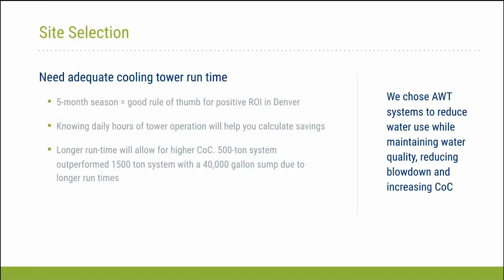So, for example, you can have a 500-ton tower running 24/7, and you'll get more savings from that than one running your typical 10 hours a day. The other piece we look at is that we typically have harder water here, not as good water quality, so that lowers our savings potential, whereas somewhere with softer water that you're not having to treat gives you more capability.